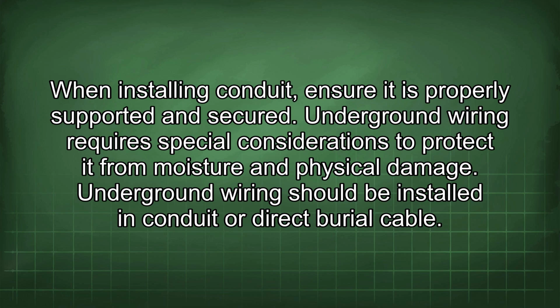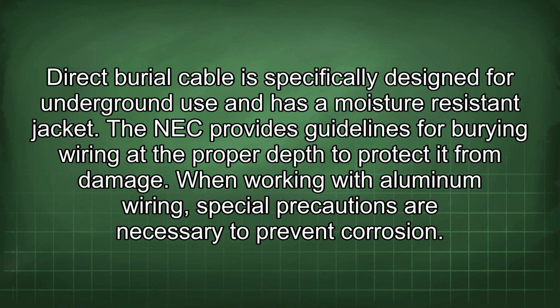Underground wiring requires special considerations to protect it from moisture and physical damage. Underground wiring should be installed in conduit or direct burial cable. Direct burial cable is specifically designed for underground use and has a moisture-resistant jacket. The NEC provides guidelines for burying wiring at the proper depth to protect it from damage.